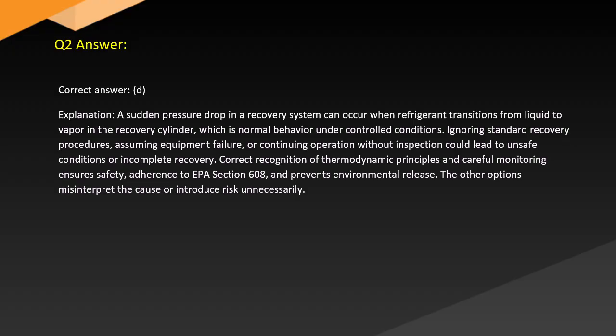Answer. Correct answer: D. Explanation. A sudden pressure drop in a recovery system can occur when refrigerant transitions from liquid to vapor in the recovery cylinder, which is normal behavior under controlled conditions.